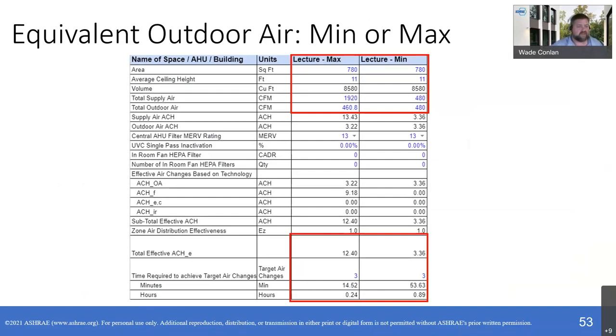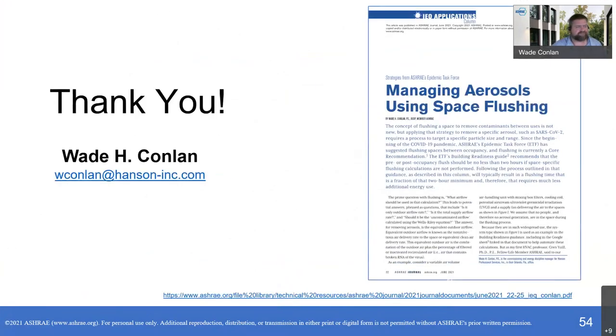Now, they had MERV 13s and a lot of air. But if your design says at my max airflow I'm doing 6 equivalent outdoor air changes, well, if I get into heating now, I might be down at 3.6 or 4. Is that okay? So you have to understand where your system is actually operating with its airflow. It plays a very big part when it comes to figuring out your equivalent outdoor air. Next slide, please. This is an article that gets into a lot more detail.